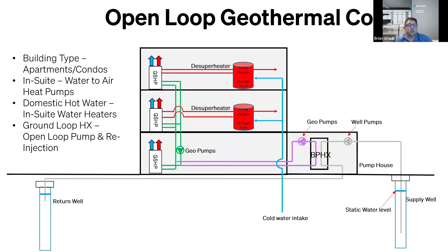We have some supply wells because the underwater hydraulic movement of the water goes from the southwest to the northeast. So we put all the supply wells on this side and the return well over here. The heat being put into the ground would be dumped and follow the direction of the underground flow and dissipate before getting recirculated back to the supply wells. So there are two, for redundancy, supply wells, and one reinjection well for each energy center.